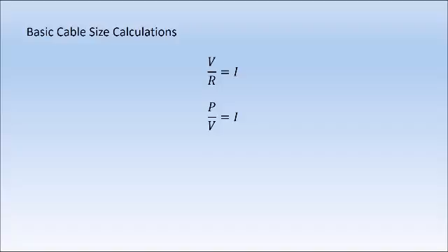Current carrying capacity is determined usually by the size of the cable, but also the type of insulation around the cable itself. You've got PVC insulations that range from about the 60-degree mark up to 120 degrees. So a 60-degree PVC insulation will have a lower current carrying capacity than a 120-degree PVC insulation.